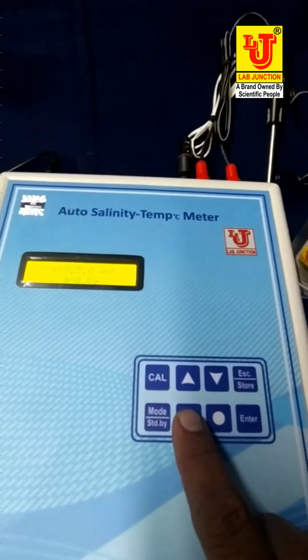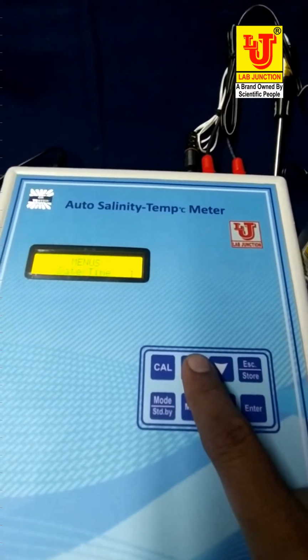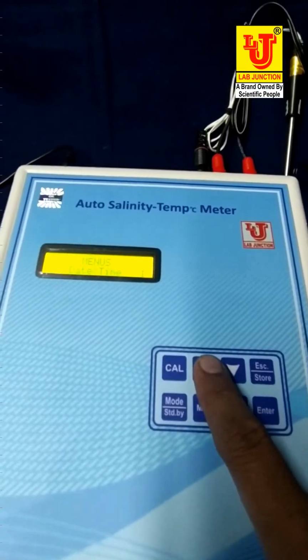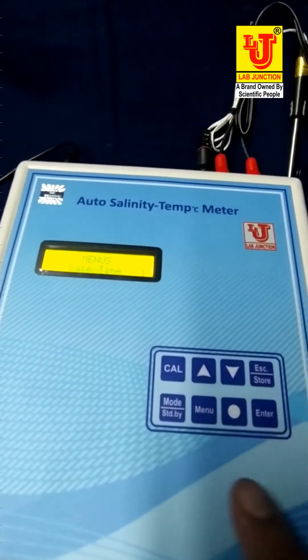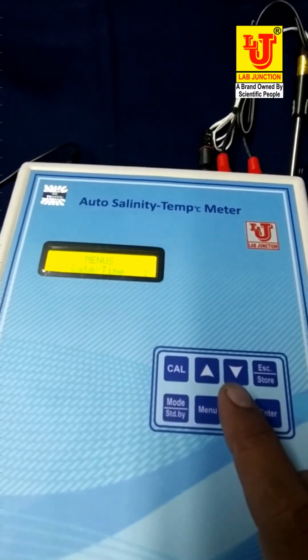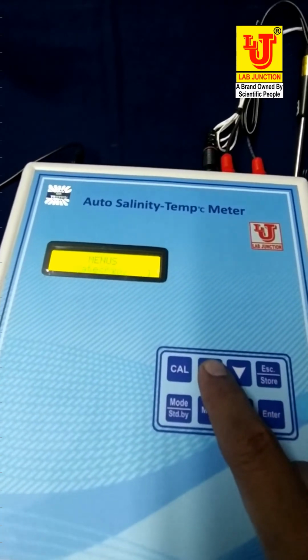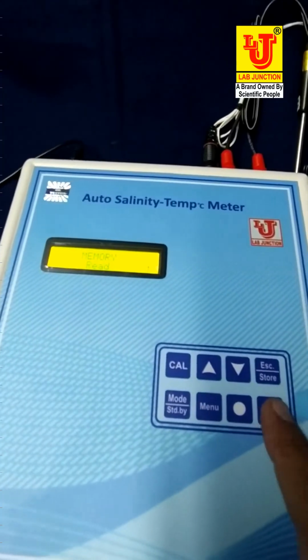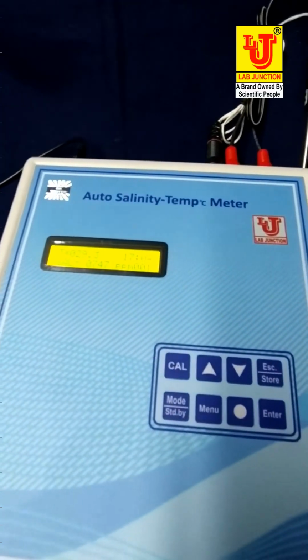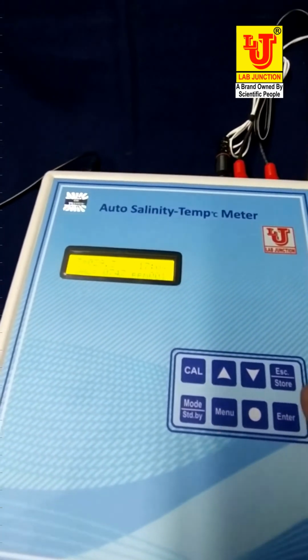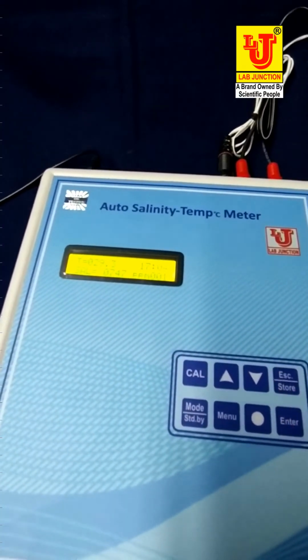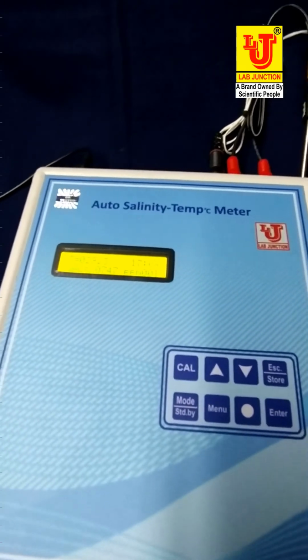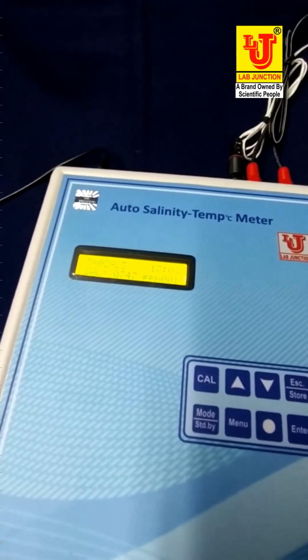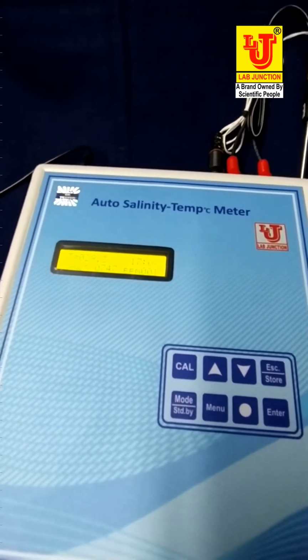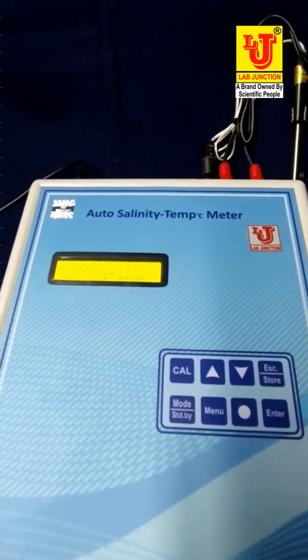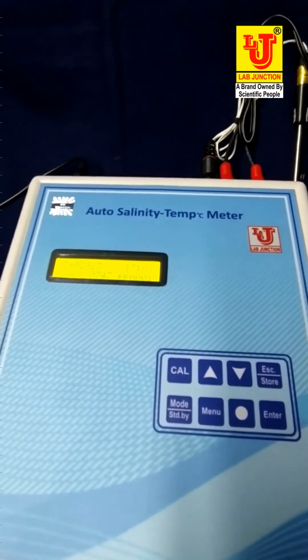This instrument also has memory like this. In this is date and time. If you want to change date and time, directly press enter and feed correct date and time from up and down key. This is memory. This is memory result. Suppose anything you have on display, then press store key, it automatically stored in instrument memory. When you see your result on the display, if you want to save in memory, directly press store key, it automatically stored in instrument memory.